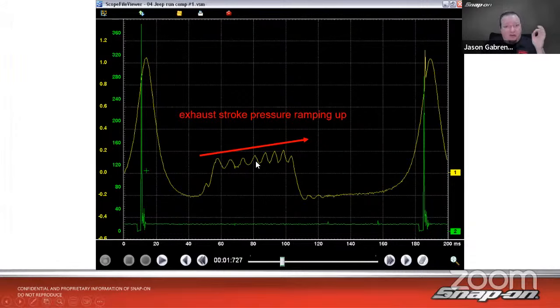This calibrates to whatever atmospheric pressure is where you're at. So you don't want to be connected to the vehicle at that point either. It's going to be relative to whatever 14.5 PSI or whatever at sea level. It's going to be relative to wherever you're at. If you're in Denver, it's going to be a little bit different than if you're down where I'm at sea level. So just remember, you want to calibrate it every time.